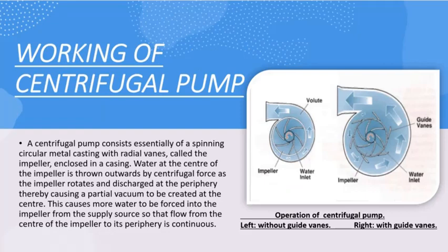The main key element of a centrifugal pump is the impeller. It has an eye at the midsection through which water flows in. When you prime the pump, it creates an initial suction at the eye of the impeller, causing water to flow in. As the water enters, the rotating impeller throws it towards its periphery, again creating a partial vacuum at the center which allows more water to enter. This continues, and the water thrown to the periphery is collected through the volute casing and discharged.